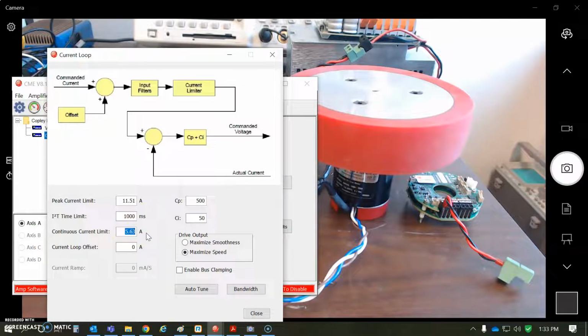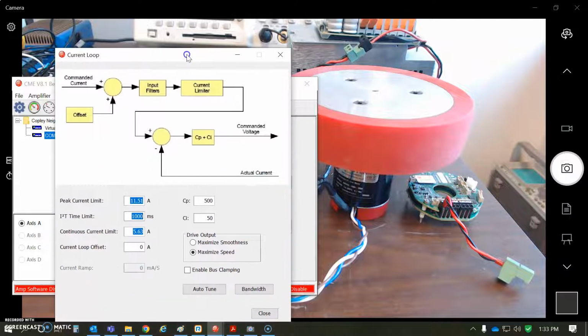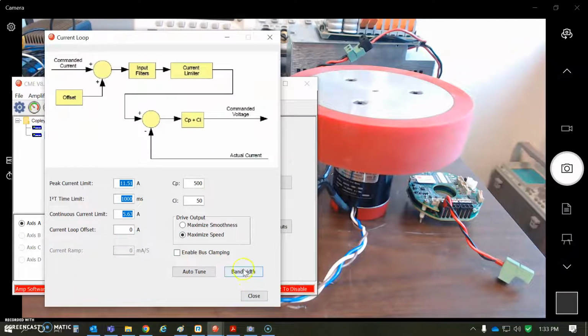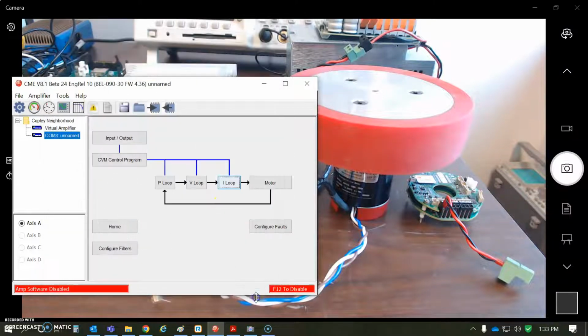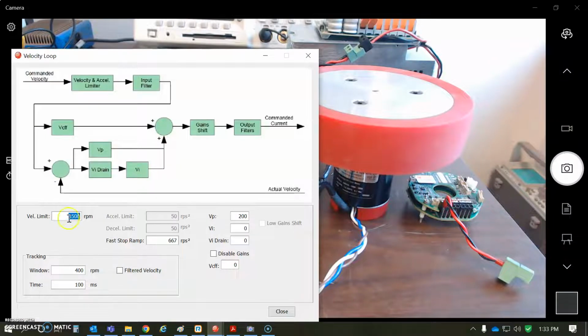So the current is in amps peak, 5.63 amps peak, so less amps RMS, but twice that approximately for acceleration. We can do that for a second or for 10 seconds, or not sure how long that is for this motor, so maybe it's 5 seconds. Just be careful not to burn up your motor if you increase the time. The drive, of course, could do 30 amps peak, 15 amps forever, so not a problem. Typically about a kilohertz of current loop bandwidth, even for a 14-pole motor, not going wicked fast, should be fine. And the absolute theoretical maximum speed is just for safety, you could lower it. You're not going to go more than 3,000 anyway.